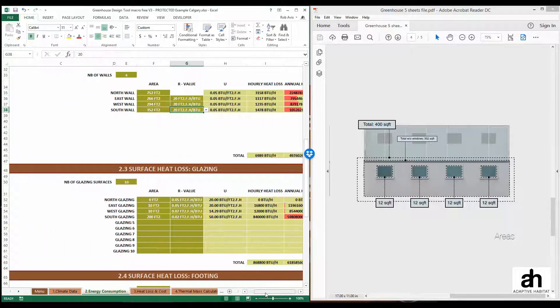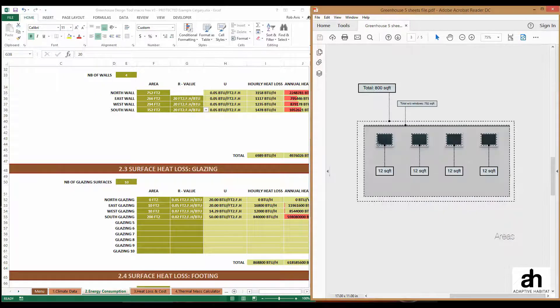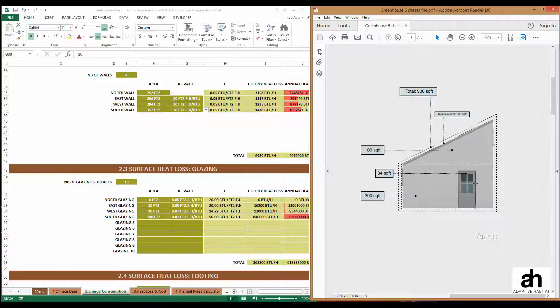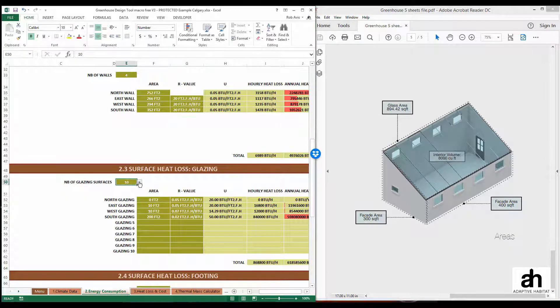Section 2.3 — we're going to calculate surface heat loss out of the glazing. The number of glazing surfaces is dictated by the number of different areas within the respective orientation: north, east, west, and south, not including the primary glazing area on the top of the greenhouse. The south facade is one glazing surface. The main glazing area on top is one independent glazing surface. The northern wall is one glazing surface. The west and east glazing surfaces are each one area — the east being the door. So we're going to enter five different glazing areas.